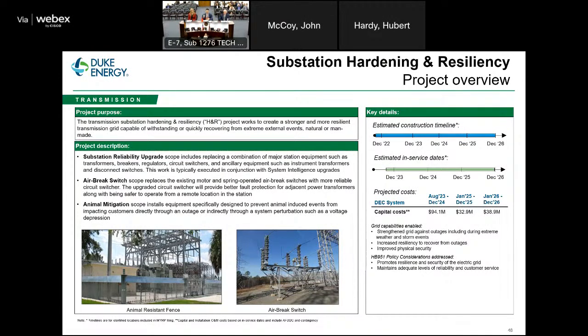Our air-break switch scope is a specific project targeted at a technology or a design called an air-break switch. This is used in our 44 kV and 100 kV locations. It is on the high side of a power transformer. And really what it is designed to do is to interrupt a fault and protect the power transformer from damage. In a substation, the most expensive and the most critical asset is the power transformer. And when transformers fail, they often result in a catastrophic failure, collateral damage to adjacent equipment, potential for release of oil. So it's very important for us to protect them. The air-break switch is a device that protects them. What we're doing is actually upgrading these with a device called a circuit switcher. That has an improved ability to actually interrupt the fault and protect that downstream transformer.